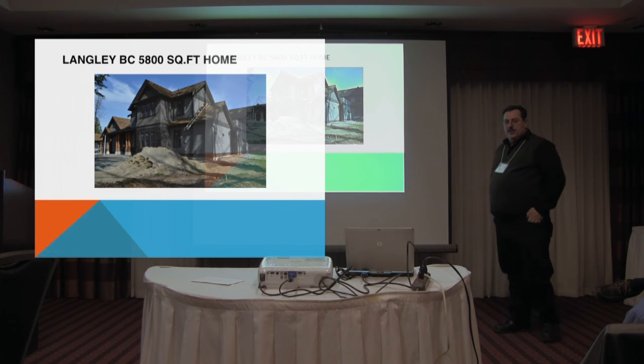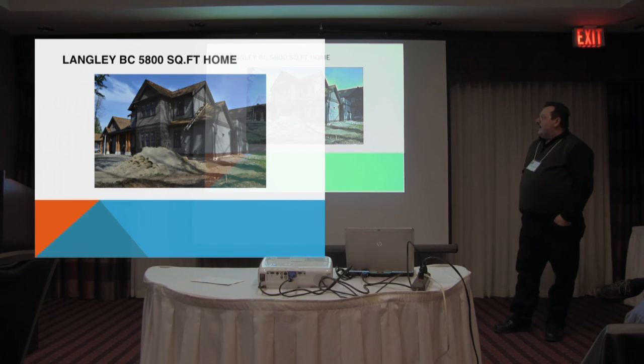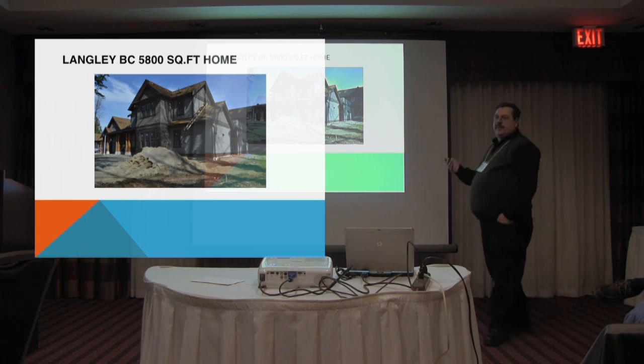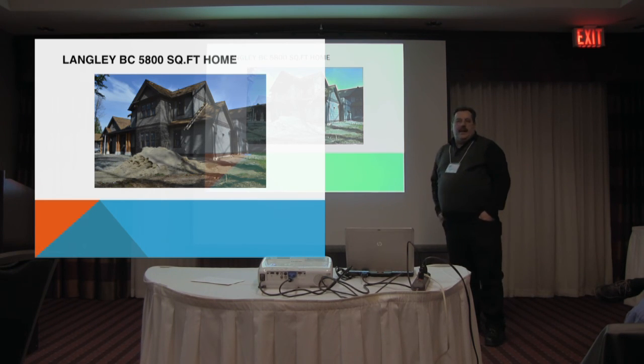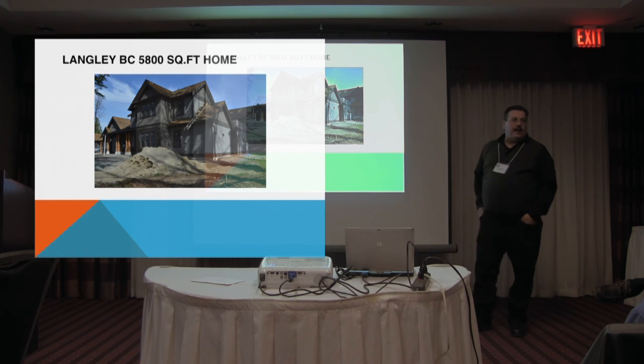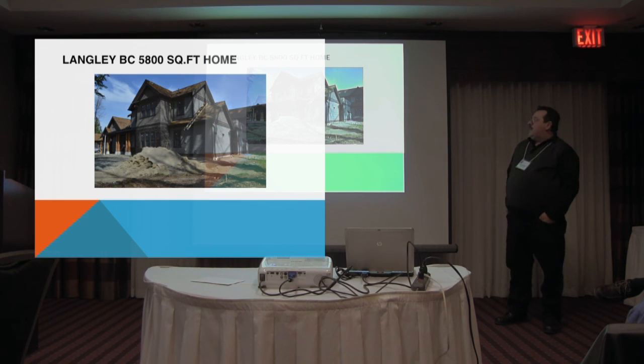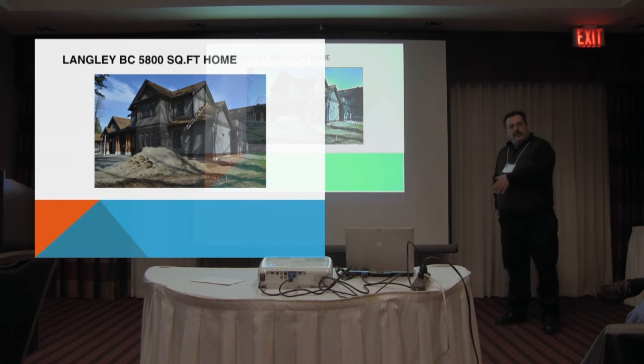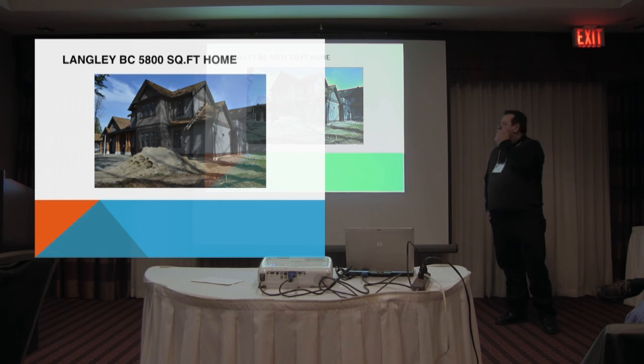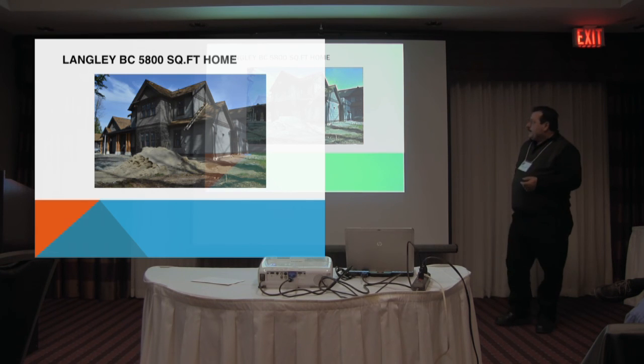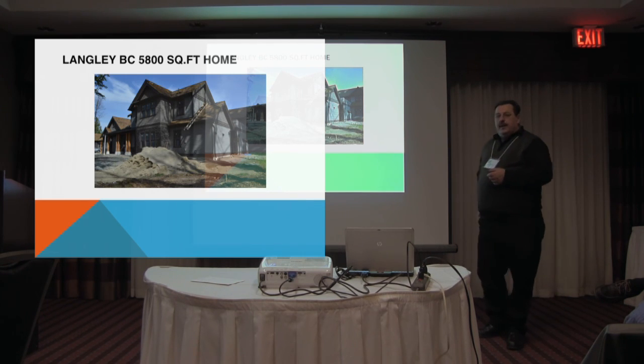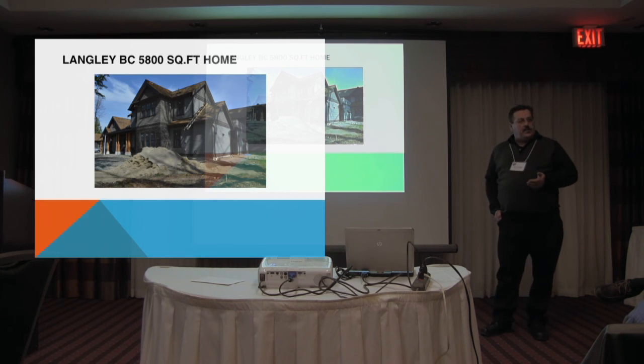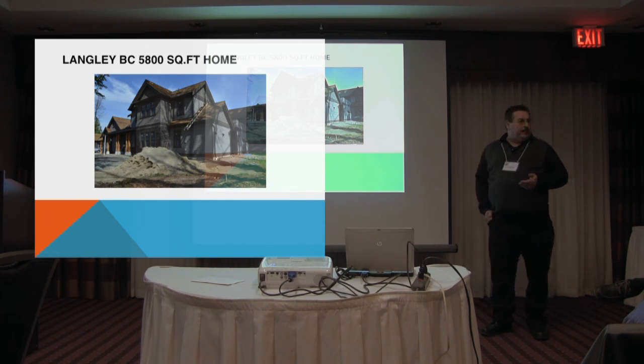Here's a house. This one's in Langley, and it has 1 CHP unit in it. Now this house is 5,600 square feet. It has an outdoor pool, and it has an outdoor hot tub. It's got radiant floor heating throughout. The house is slab on grade, and it's kind of like a U shape, so there's a lot of slab edge. So it's really an inefficient house to begin with in terms of design and development, for 5,800 square feet. The pool is heated during the summertime, it's turned off during the wintertime. But the hot tub is kept going all winter long. All right, so it's got a good annual thermal load.